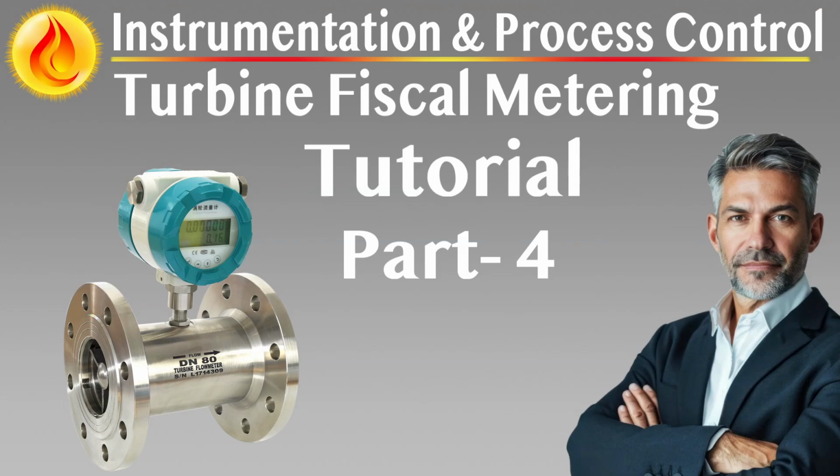Meter prover, inline calibration for continuous traceability and legal verification. The meter prover is a fundamental component of the fiscal metering system, providing direct calibration of turbine meters under live process conditions. Its purpose is to establish the actual meter K factor by comparing measured pulse counts against a known traceable volume, ensuring the turbine meters operate within acceptable uncertainty limits over time.